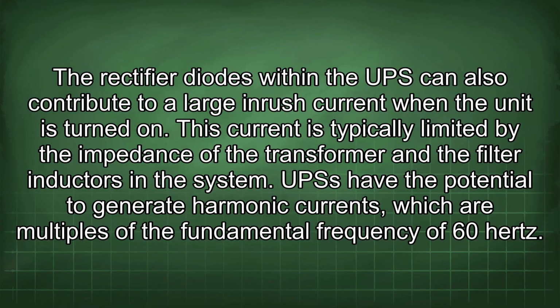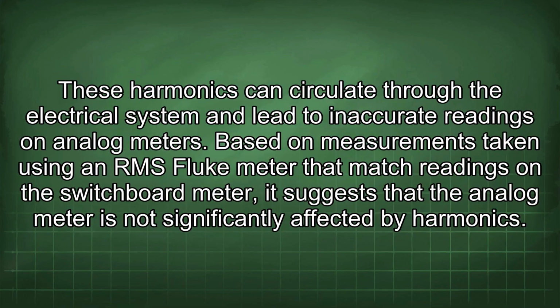UPS have the potential to generate harmonic currents, which are multiples of the fundamental frequency of 60 Hz. These harmonics can circulate through the electrical system and lead to inaccurate readings on analog meters. Based on measurements taken using an RMS Fluke meter that match readings on the switchboard meter, it suggests that the analog meter is not significantly affected by harmonics.